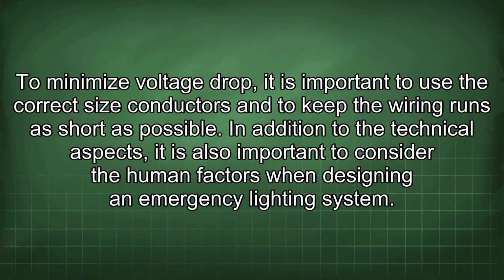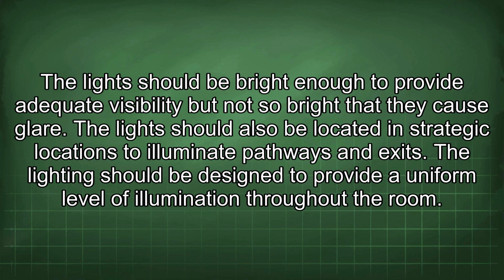In addition to the technical aspects, it is also important to consider the human factors when designing an emergency lighting system. The lights should be bright enough to provide adequate visibility, but not so bright that they cause glare. The lights should also be located in strategic locations to illuminate pathways and exits. The lighting should be designed to provide a uniform level of illumination throughout the room.